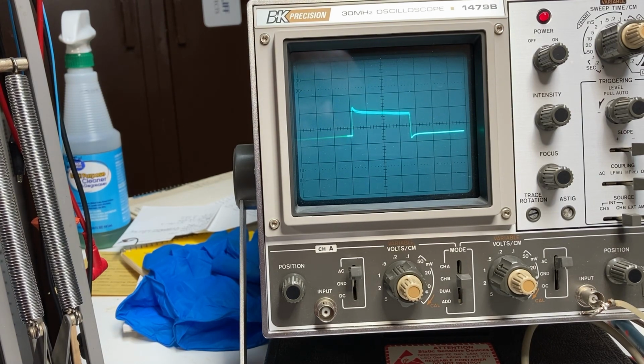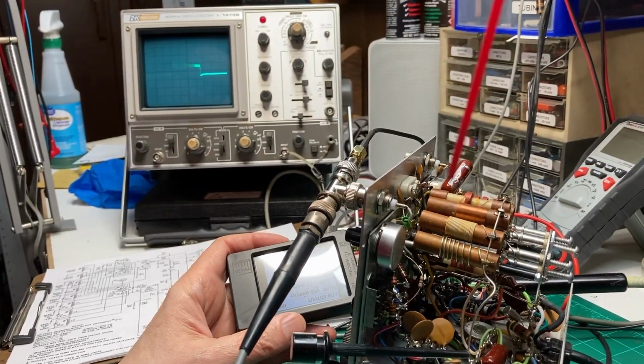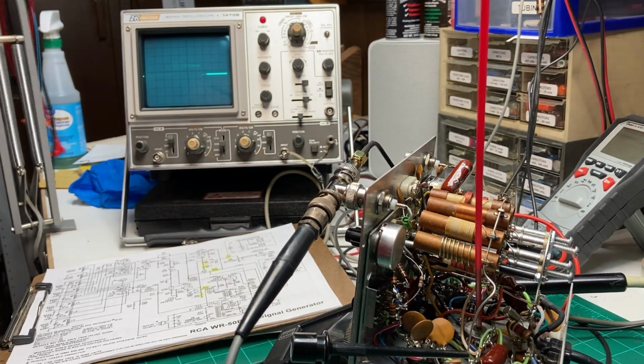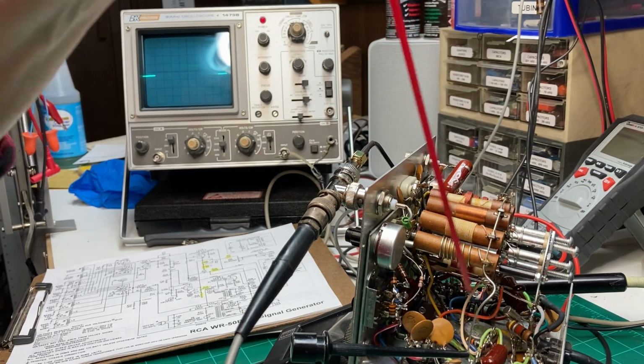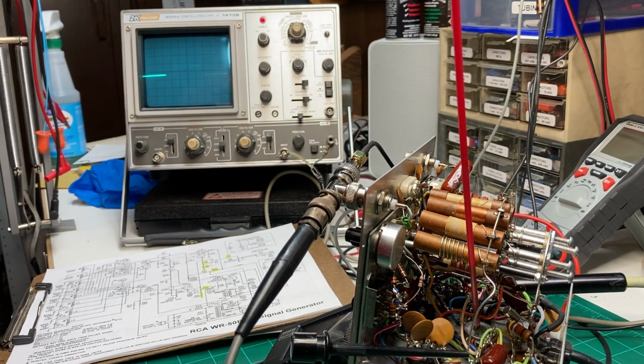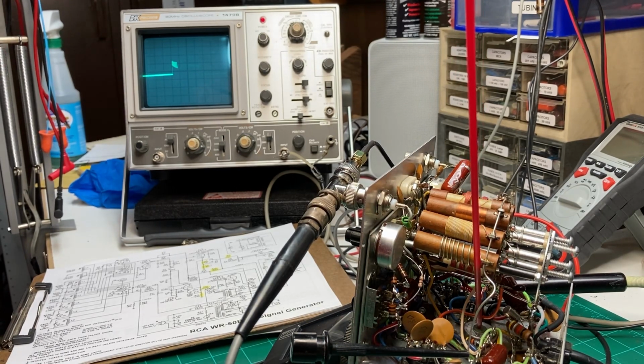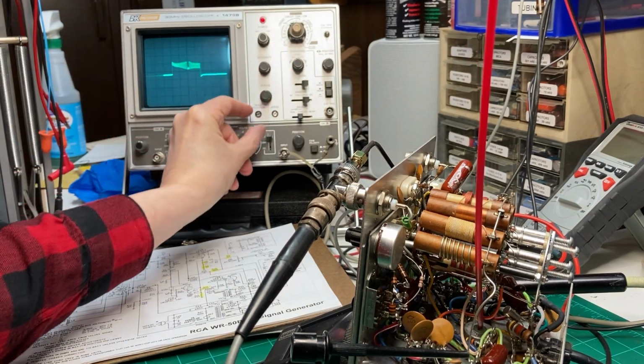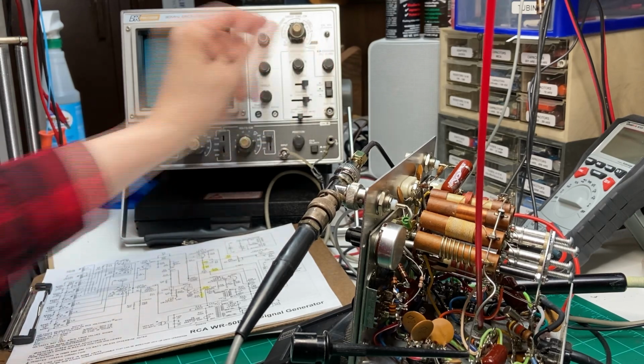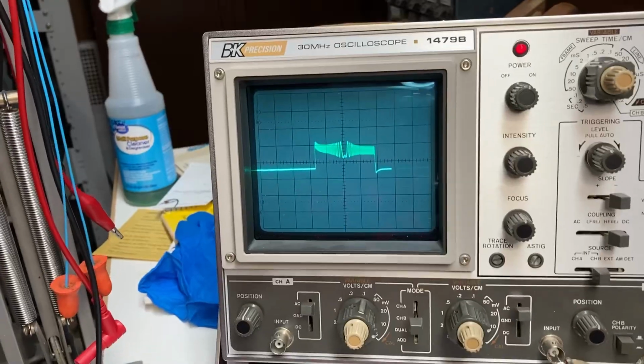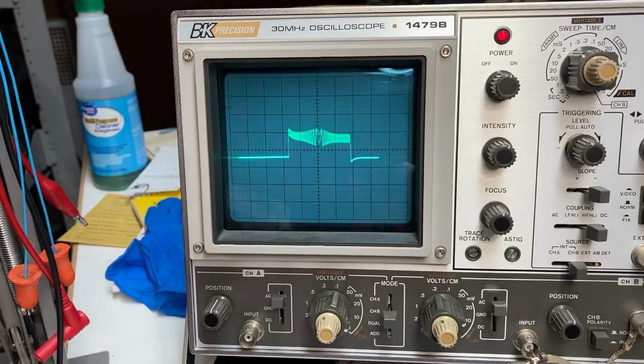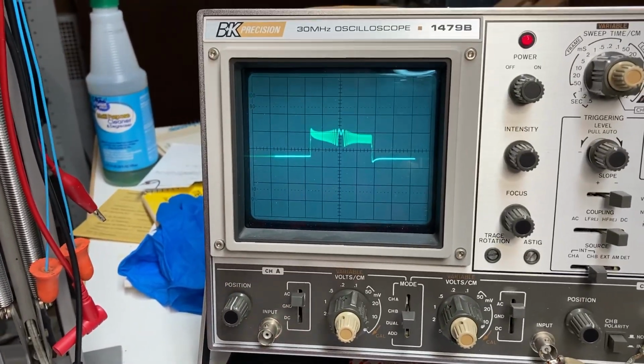And I'm going to turn this off. That's the marker, and then back on again. Now with it back on, we're going to go over here, and I'll show you where to adjust this. It's this pot right down here. Get a little light on it so you can see a little bit better. And we're going to adjust that to where that marker will be right in the center of the sweep. Okay, now we got that whole thing right there. Let's go ahead and turn R9 until it centers up right in the center of the, let me adjust this position here a little bit so it's better centered. There we go. Now we'll adjust that right to the center, you see. And now we can see that the marker right here is directly in the center. So we know we have this linearity adjustment on R9 perfectly done.